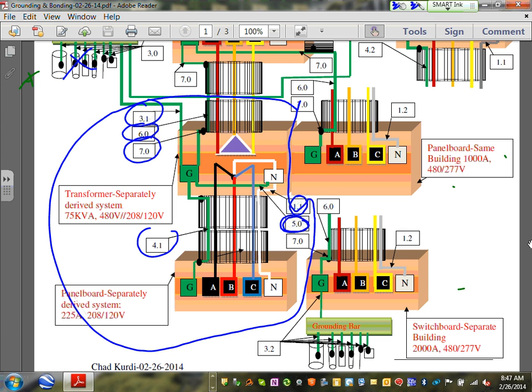Then we have to do a supply side bonding jumper. Have you noticed when we were looking at transformers yesterday, they have a flex? They have a flexible metallic conduit tie the panel to the transformer. Inside that flex, they pull a wire. That wire that they pull to tie the transformer to the panel, ground bonded together, is called the supply side bonding jumper. You're looking at it right here.